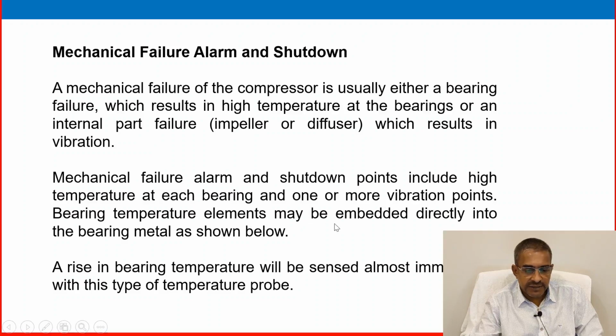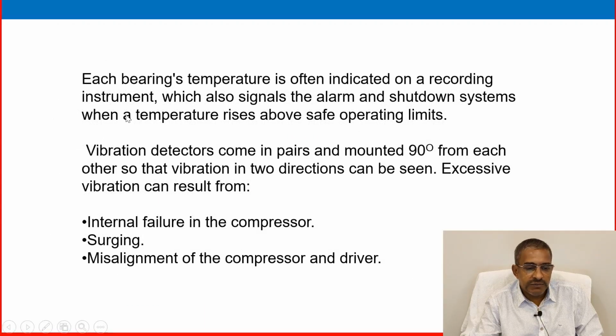Bearing temperature elements may be embedded directly in the bearing metal as shown below. A rise in bearing temperature will be sensed almost immediately with this type of temperature probe. Each bearing's temperature is often indicated on a recording instrument, which also signals the alarm and shutdown system when the temperature rises above the safe operating limit.